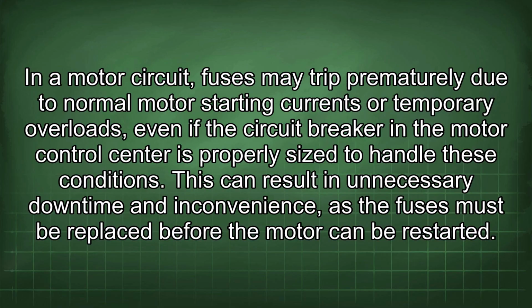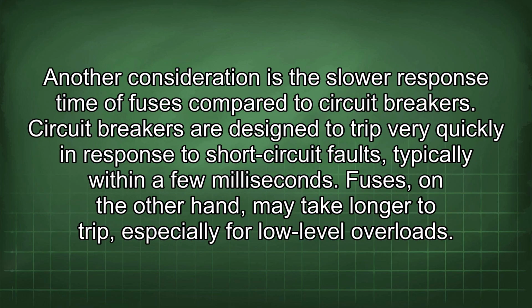even if the circuit breaker in the motor control center is properly sized to handle these conditions. This can result in unnecessary downtime and inconvenience, as the fuses must be replaced before the motor can be restarted. Another consideration is the slower response time of fuses compared to circuit breakers. Circuit breakers are designed to trip very quickly in response to short-circuit faults, typically within a few milliseconds.